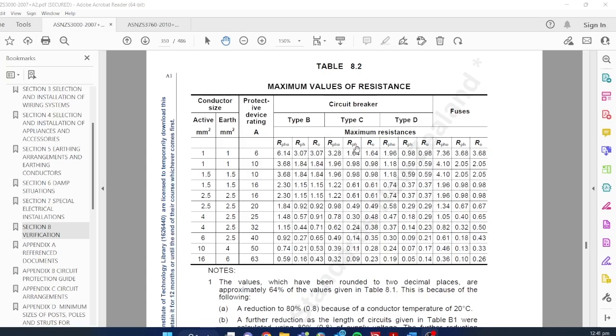And we've got three columns here. It says RPHE, RPH, and RE. RPH is resistance of the phase wire. RE is the resistance of the earth wire. RPHE is the resistance of the two together. And that's interesting because if we think about the way we did that test, we tested the phase and earth conductor together, and we got a reading of about 0.4 ohms. So this table here is giving us that value to allow us to do the test in that way, to test that phase and earth together with the link between the main switch and earth busbar in our switchboard.